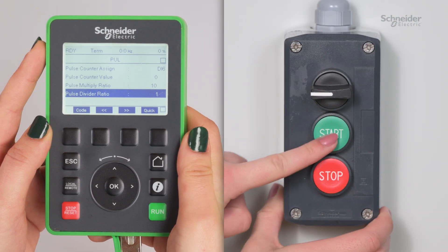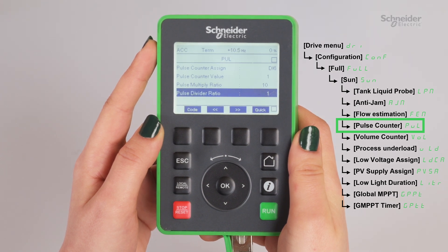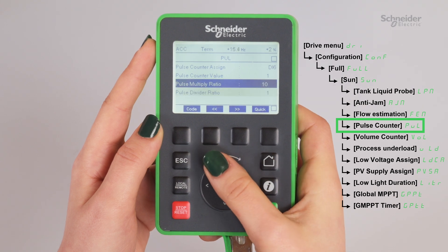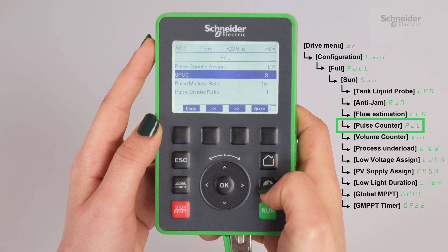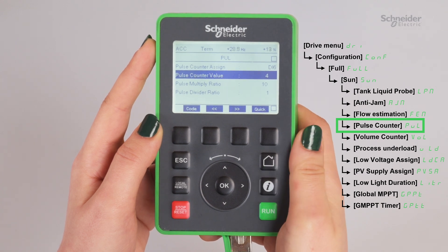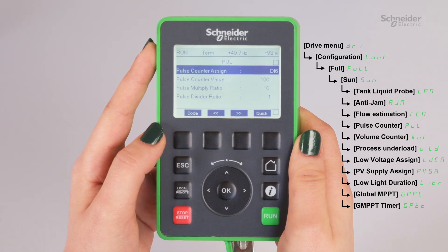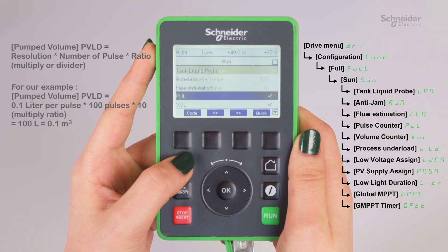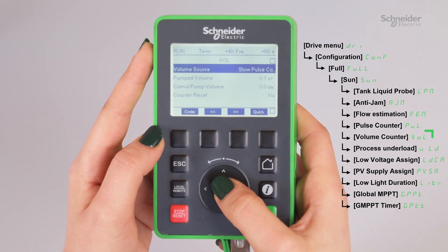Start the pump. Check Pulse Counter Value and wait until it has reached 100 pulses. Go to Volume Counter and check that the estimated flow rate, Pumped Volume, reaches 0.1 meters cubed.